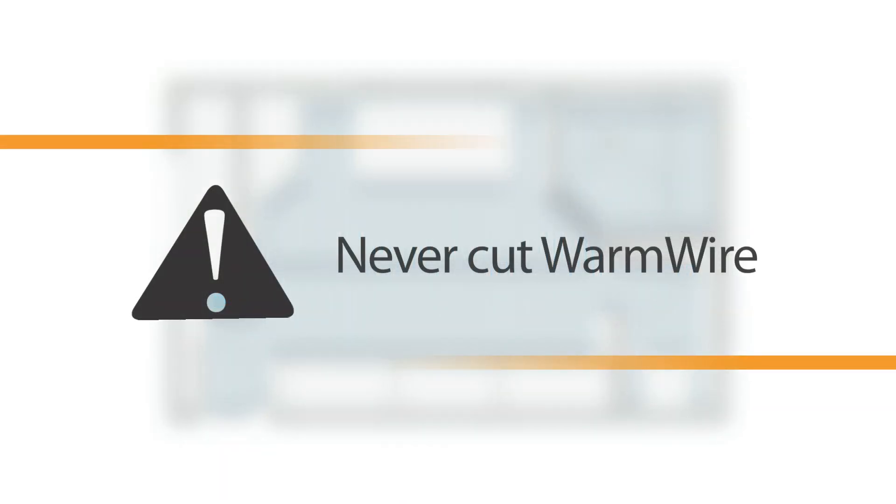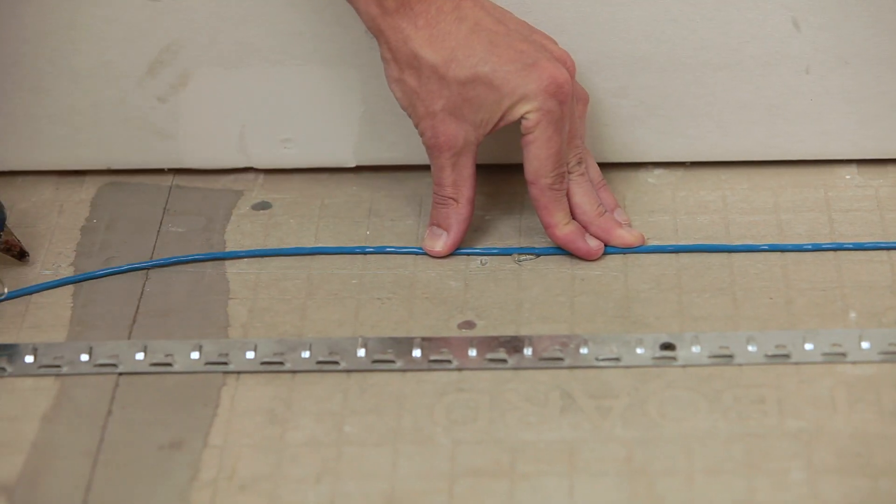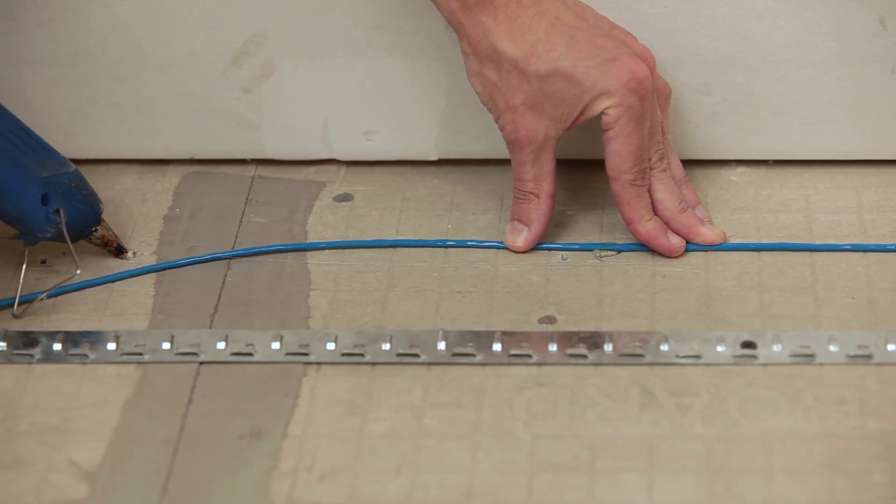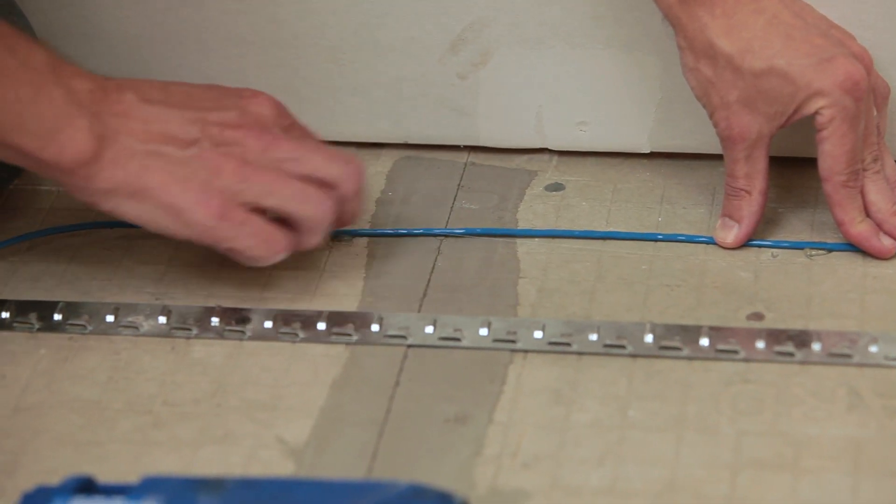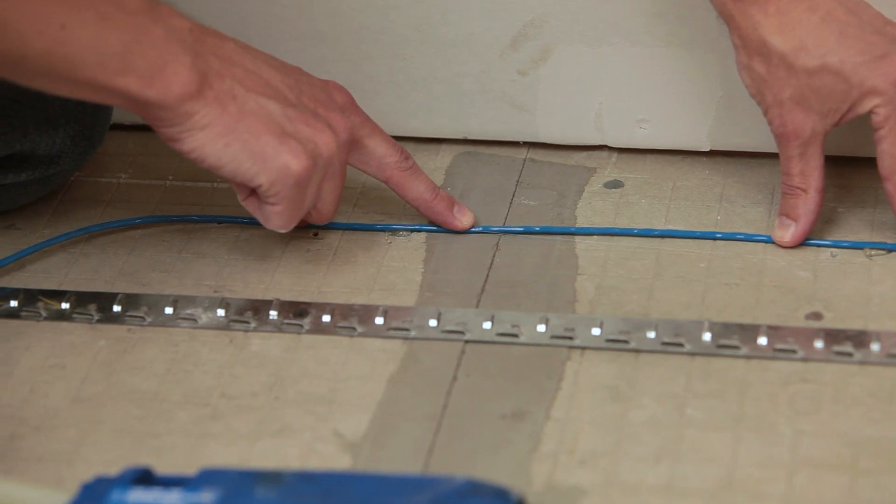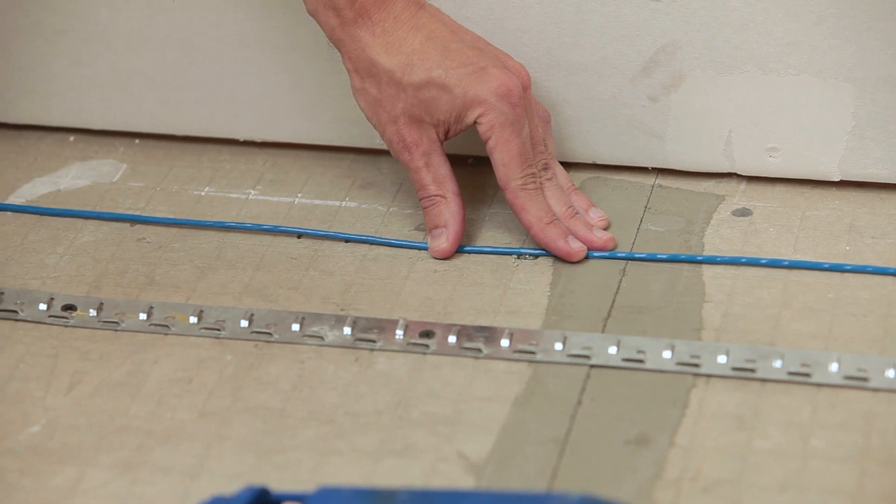This can cause dangerous overheating and will void the warranty. You may also consider using the additional wire along a perimeter or an area where heat isn't needed but will do no harm. Do not extend the wires into areas that will not have the same mortar and floor treatment and do not place the wire where it will be covered later by trim work or built-ins.